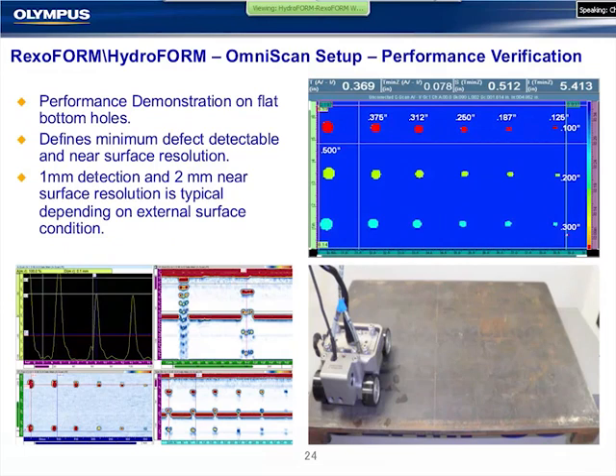Prior to the inspection, also, in addition to the calibration, probably the most common question we get asked is, what is the smallest defect this can find? And what is the minimum separation between two small defects that this can differentiate? So it's not uncommon that the customers will build a performance demonstration using flat-bottomed holes. It determines both the ability to size them, the ability to detect small ones, the ability to detect near surface resolution, and it would be a series of holes at different depths and sizes that we would scan to determine if we're using the correct frequency, aperture, and so forth.